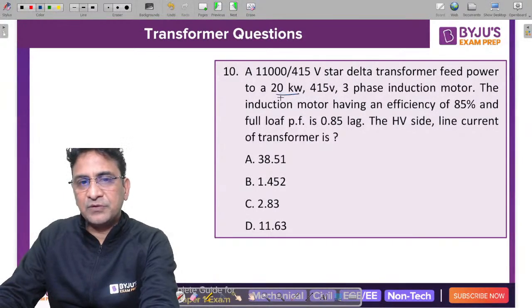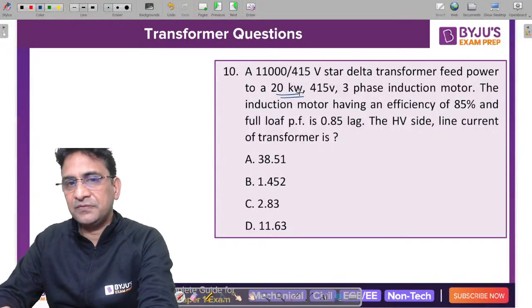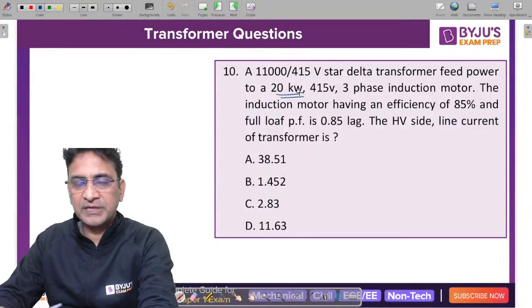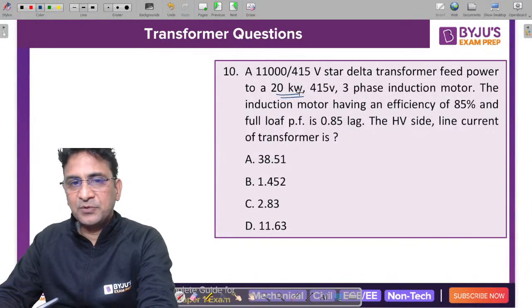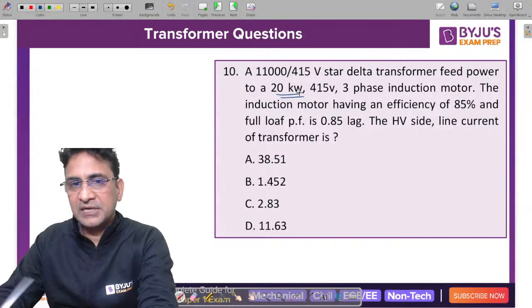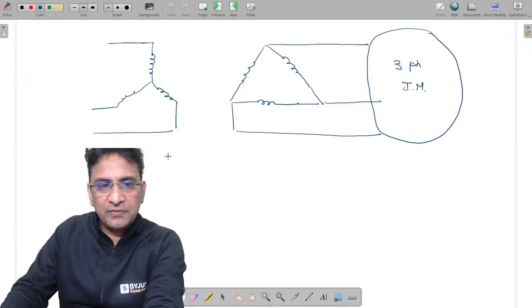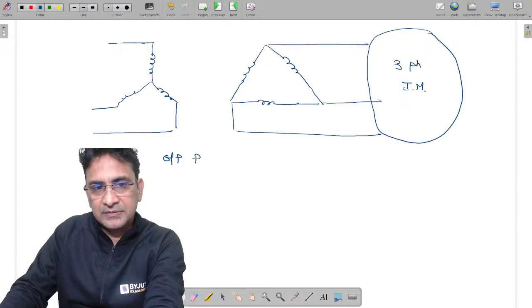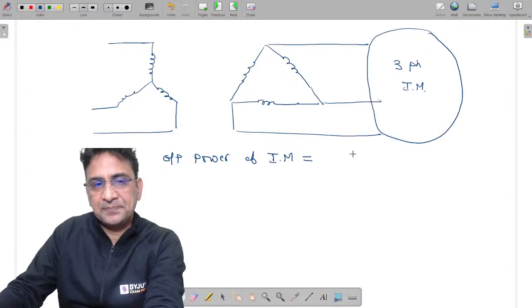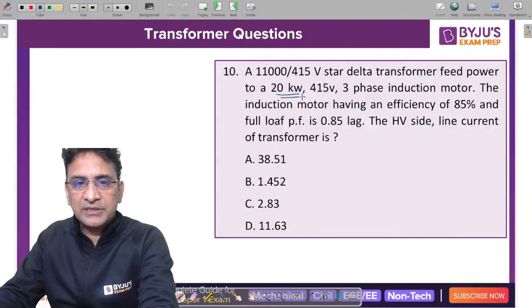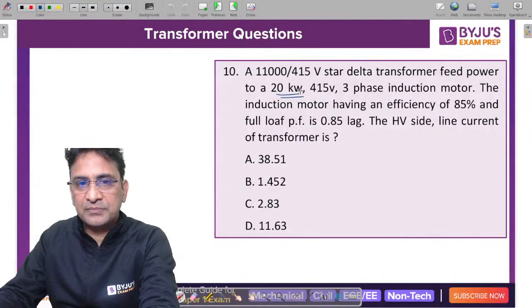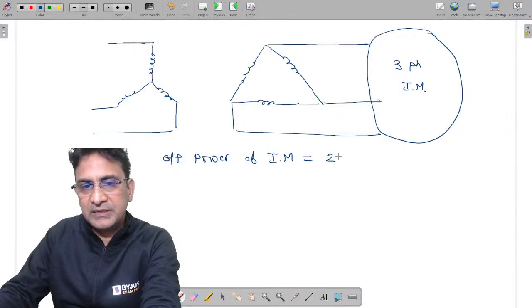What is the 20 kilowatt of the induction motor? What is the rating of the induction motor? Is it the output power or the input power? In case of a motor, the rating of the motor is always the output power. Only in case of a transformer, the output kVA and the input kVA are the same. For all other machines, the power is always the mechanical output power. So the 20 kilowatt is the mechanical output power.